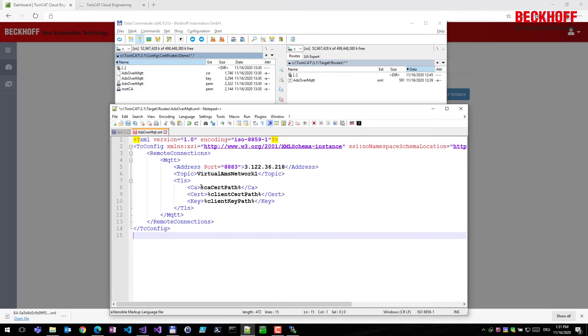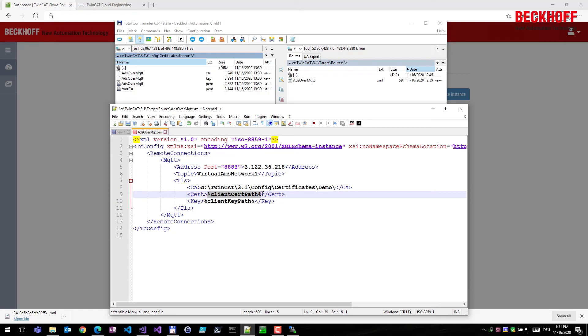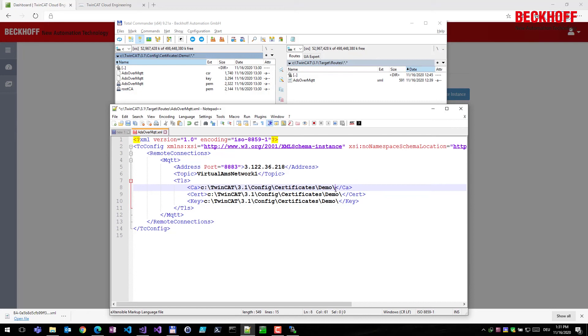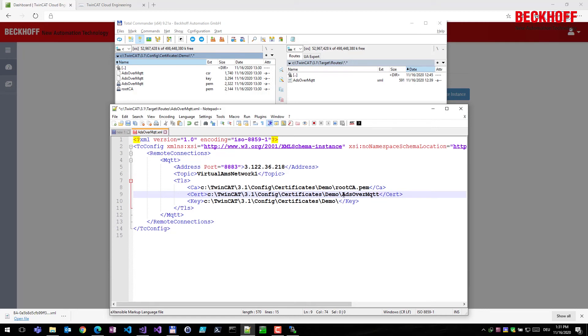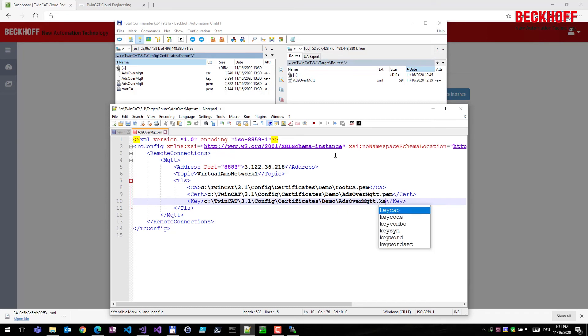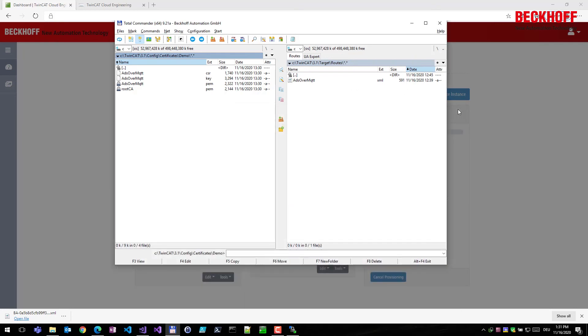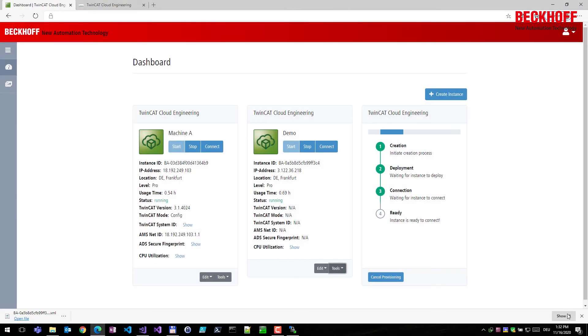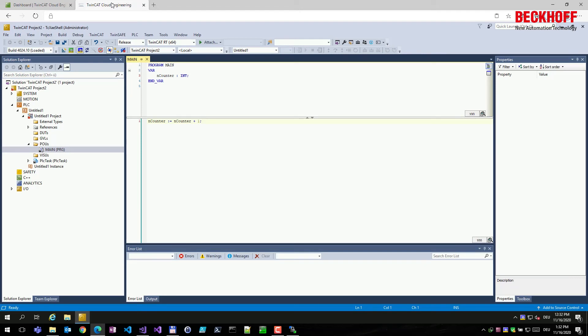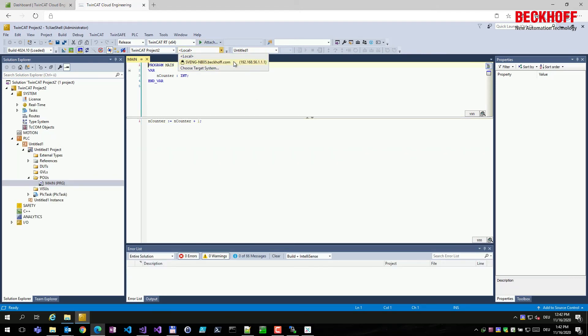Next, we generate an ADS over MQTT configuration file for TwinCAT. This XML-based configuration file is downloaded from the website and placed in a specific TwinCAT directory. It must then be modified to specify where the certificate files are stored: the CA certificate file, the client certificate file, and the client key file. After entering this information, save the ADS over MQTT configuration file.